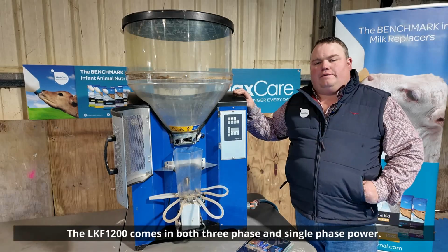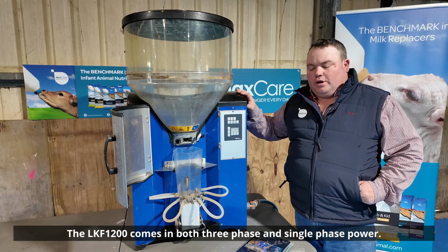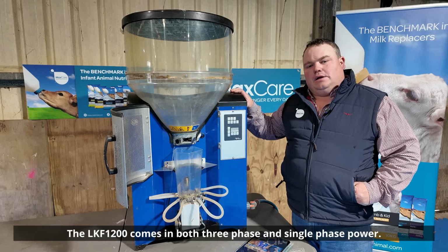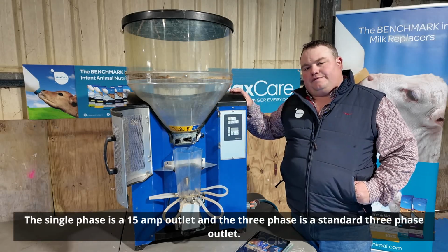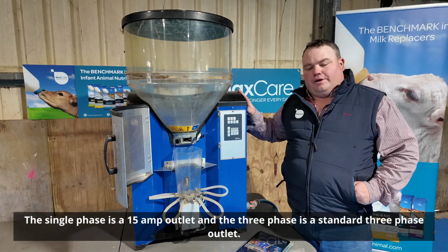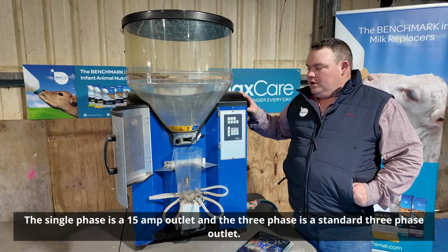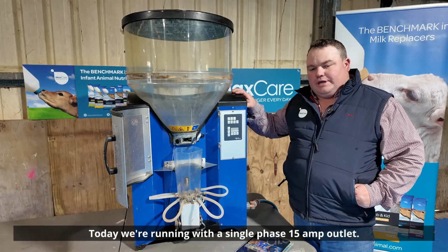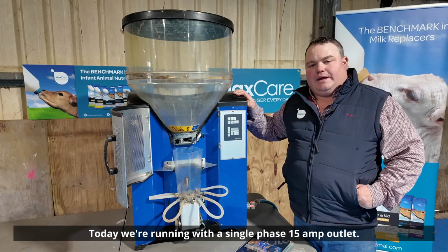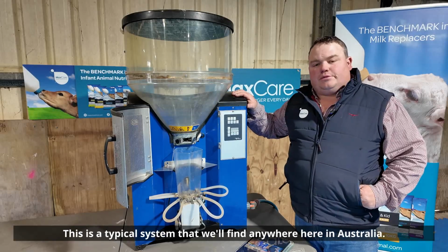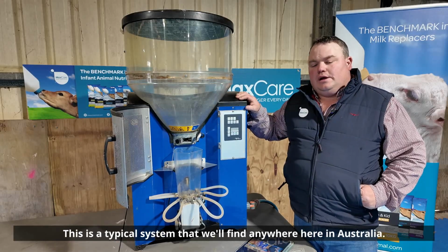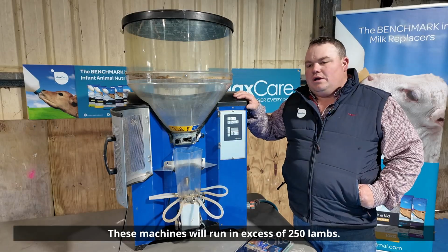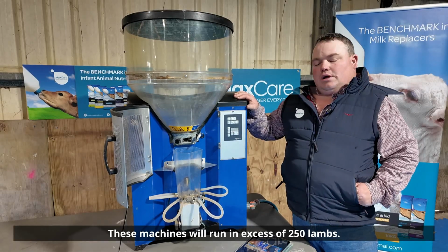The LKF1200 comes in both three-phase and single-phase power. The single-phase is a 15 amp outlet and the three-phase is a standard three-phase outlet. Today we're running with a single-phase 15 amp outlet. This is a typical system that we'll find anywhere here in Australia. These machines will run in excess of 250 lambs.